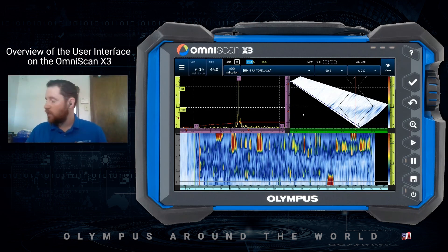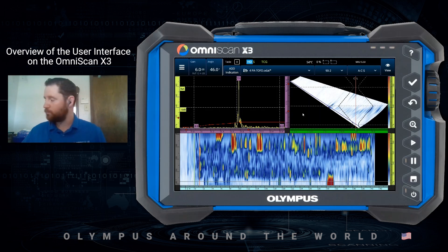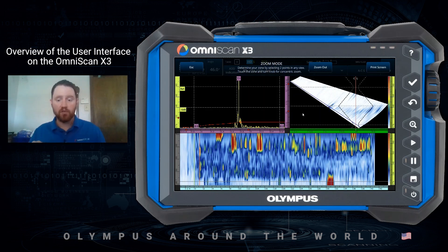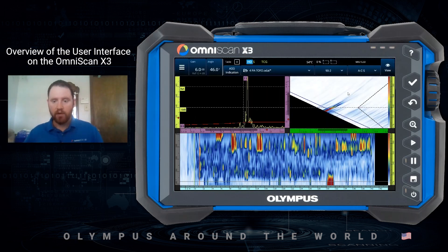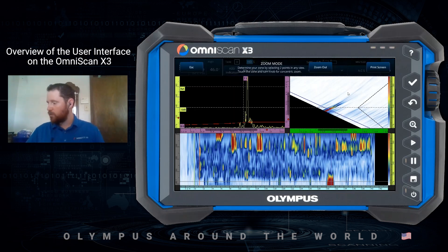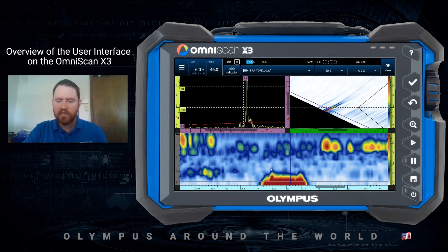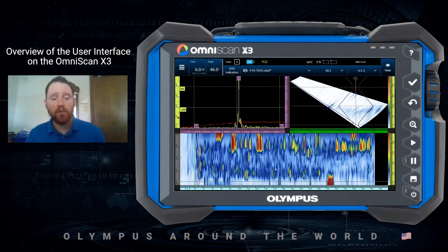An alternative way is to ignore the wheel and use what we call a two-point zoom. If I press the zoom key, it puts me into zoom mode, and I can quickly tap on two corners of the box I want to zoom in on — pressing one corner and then the opposite corner, and the instrument quickly zooms into that area. It works very quickly: press the zoom button, touch one corner, touch the opposite corner, and I can zoom into any window — the A-scan, S-scan, or C-scan display separately. Pressing the zoom key twice quickly zooms out as well.